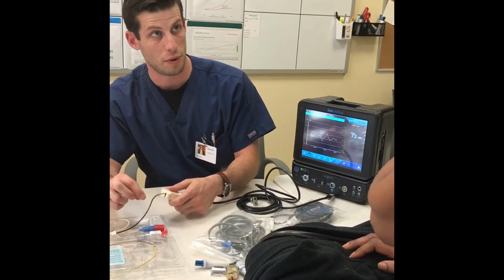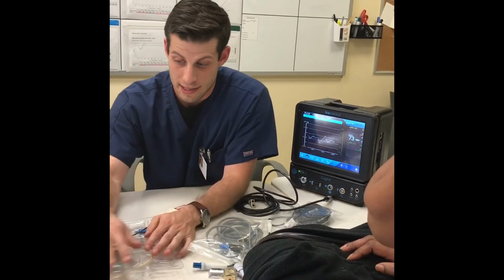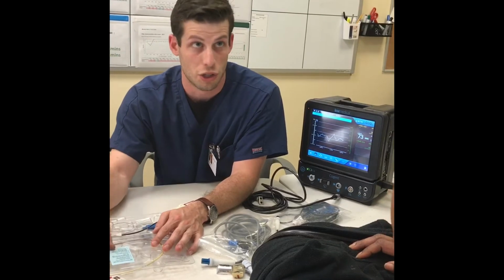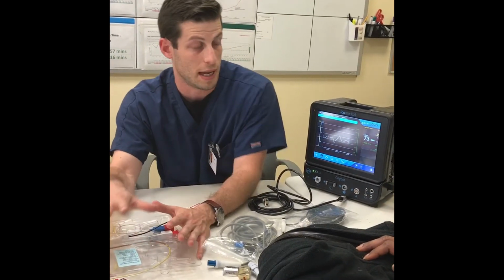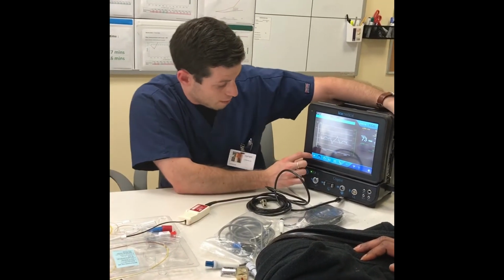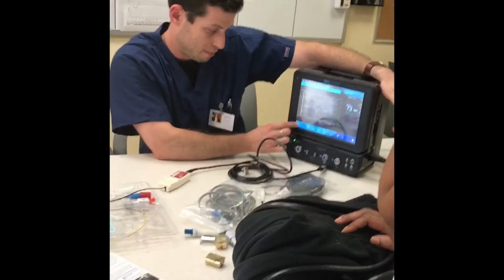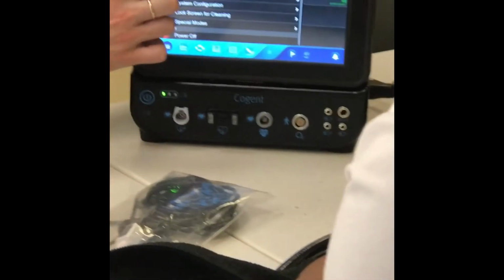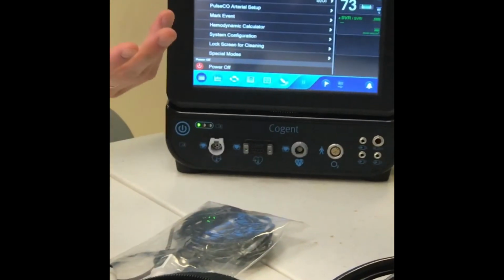Brand new. Keep in mind, this is still covered with your sterile sheath. We're not impacting the catheter. You're going to come over here, menu. Menu is a pretty simple button, a standard one these days. And you're going to go to venous O2 calibration. Makes sense because that's what we're calibrating.